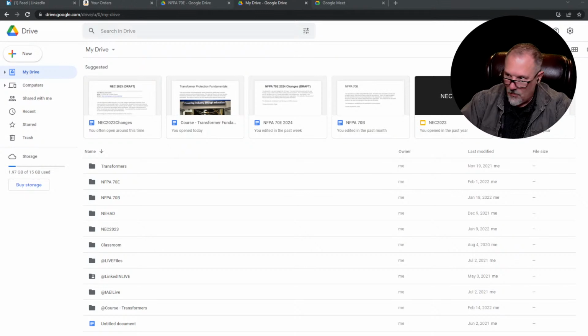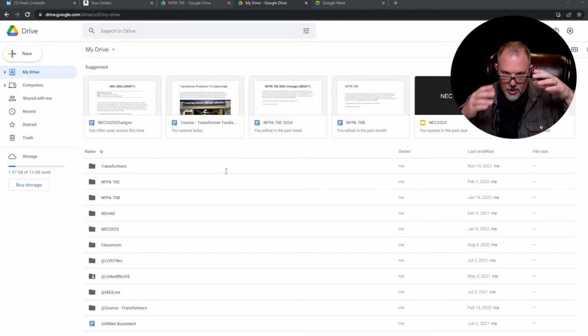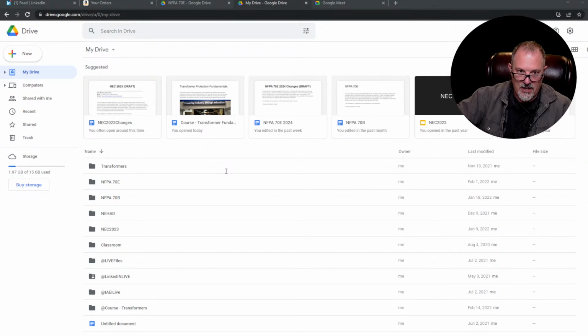So 110.4, if we recall, is no longer what it was. It's now 110.2, electrically safe work condition. And what they did was they transferred this normal operating condition into an exception. So what they're saying is you don't have to operate a circuit breaker that is in normal operating condition. You don't have to establish an electrically safe work condition because the breaker and the equipment is properly installed, it's properly maintained, and the equipment is being used in accordance with the instructions. So if you're following all of those, you do not have to create or establish an electrically safe work condition. So that was the change, and it was in 110.2.